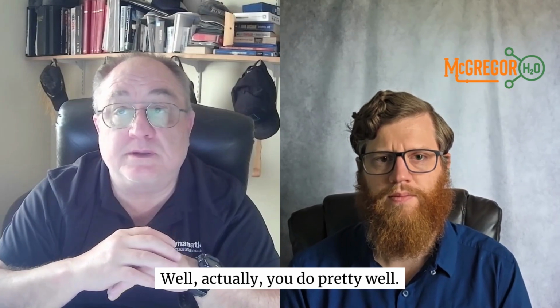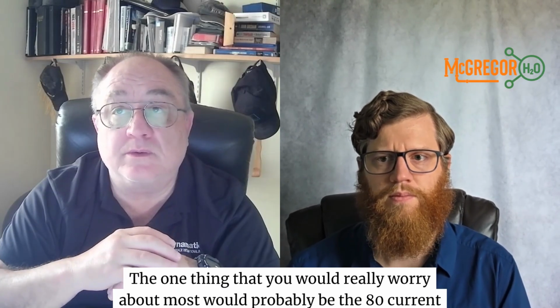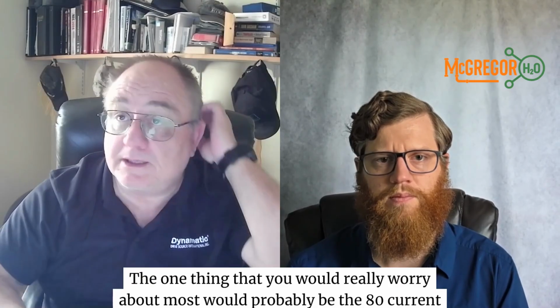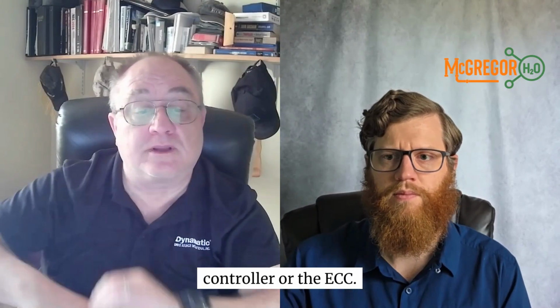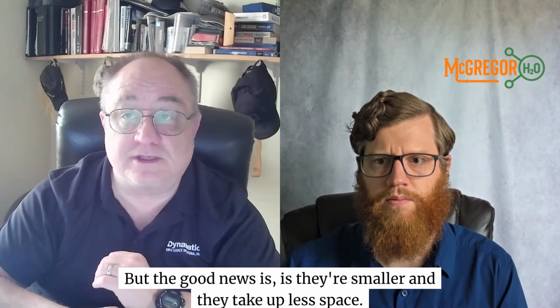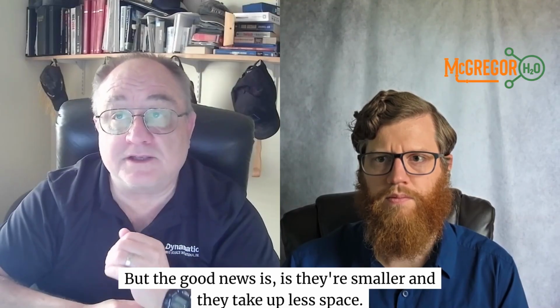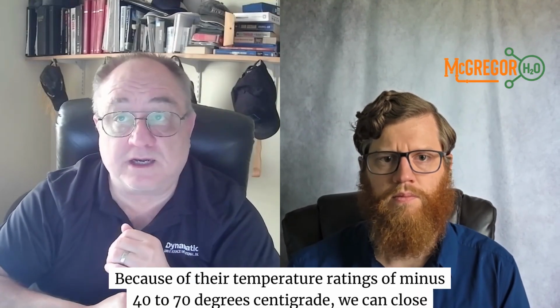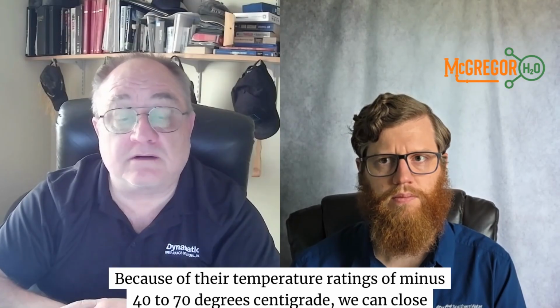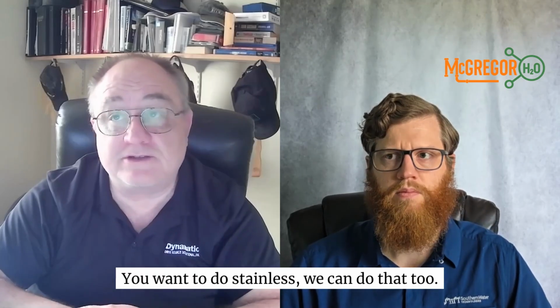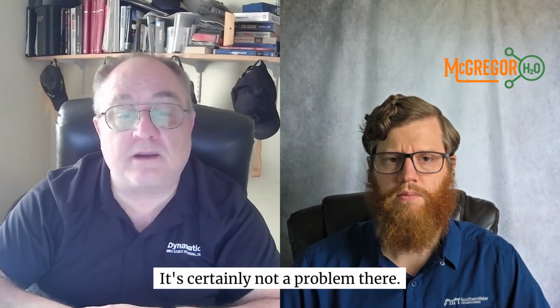Well, actually, you do pretty well. The one thing that you would really worry about most would probably be the eddy current controller or the ECC. But the good news is they're smaller and they take up less space. Because of their temperature ratings of minus 40 to 70 degrees centigrade, we can close them up in NEMA 4, NEMA 4X. You want to do stainless, we can do that too. Fiberglass, we're pretty flexible. NEMA 3R, it's certainly not a problem there.